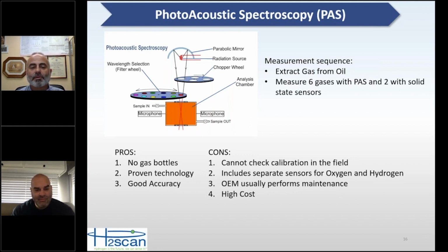The cons are generally, if you look at the specs of a photoacoustic monitor, they will specify the accuracy as found in the lab. They do use ambient air as a carrier gas, and when you're using ambient air, depending on what's in that air, it can affect the results. So a lot of times they don't guarantee the accuracy once the monitor gets in the field. Most of the monitors do not have the ability to check the calibration in the field, so you've got to rely on the consistency and on checking your monitors against your manual oil samples in order to ensure that the monitor is staying accurate.